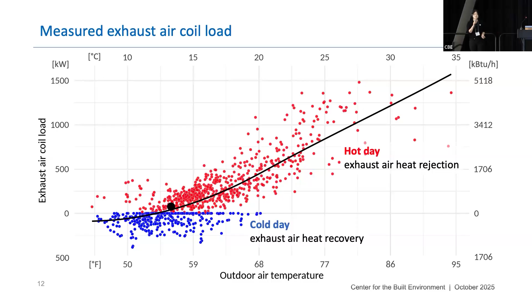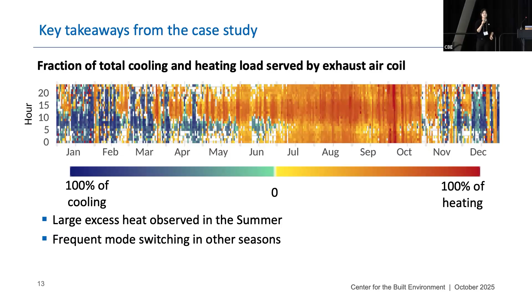This heat map illustrates how much of the chilled water and hot water generated by the heat recovery chiller was directed to the exhaust air coil. During the summer, from July to October, a large amount of excess heat is rejected through the exhaust air coil. So this means that if we could repurpose this excess heat, then we can save more energy. And for the rest of the season, there is frequent mode switching, indicating that thermal energy storage has potential benefit to increase the system efficiency.